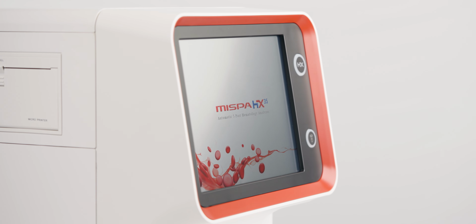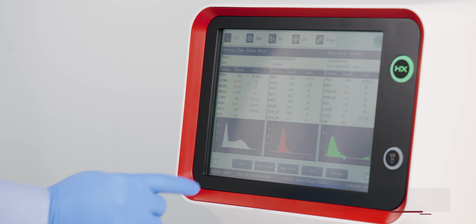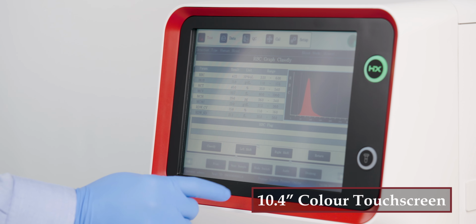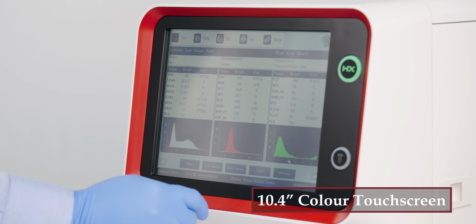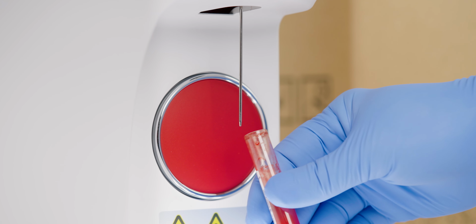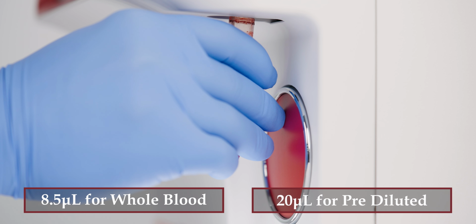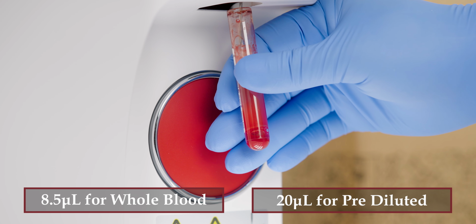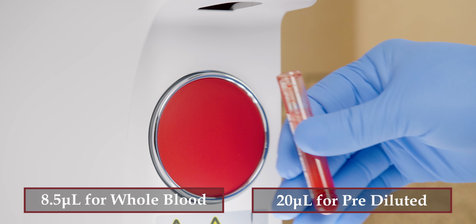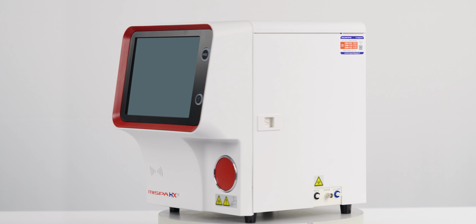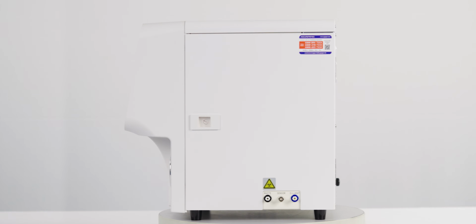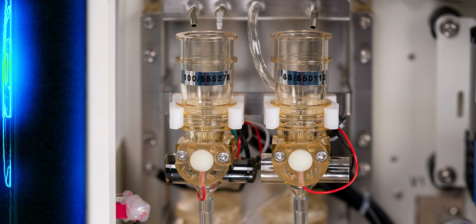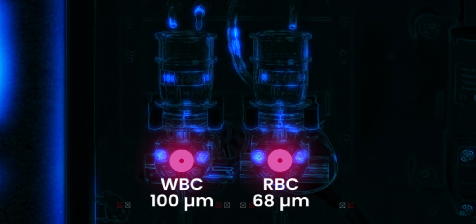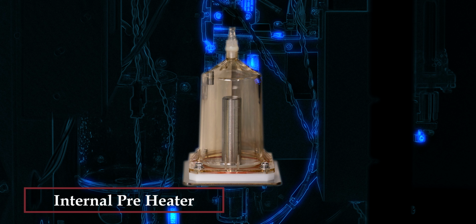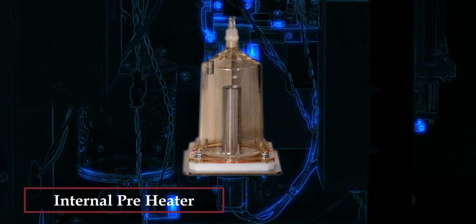Ease of use is the face of Mispa HX35. With a large touchscreen display and simple icons, operation becomes effortless. It supports whole blood and pre-diluted modes with minimal sample volume of just 8.5 microliter for whole blood and 20 microliter for pre-diluted mode. Powered by advanced transducer impedance counting technology, the Mispa HX35 ensures high accuracy and precision, made possible with its ruby aperture. With internal preheating of diluent, each test is optimized for accuracy.